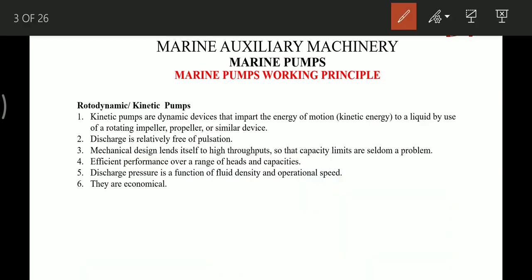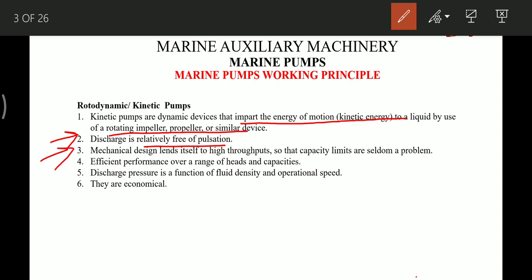A few important points about rotodynamic pumps: these pumps work by imparting kinetic energy to the liquid using a rotating impeller, propeller, or similar device. Their discharge is relatively free of pulsation — continuous and smooth. These pumps have high throughput and efficiently perform over a range of head and capacity. Discharge pressure is a function of fluid density and operational speed, and these pumps are economical.